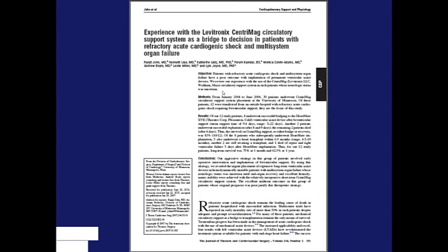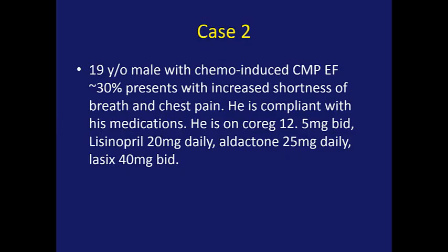So this article actually looked at 12 patients who were transferred from the outside. They implanted CentriMags in all 12. 4 of them died, but 8 of them successfully went on to HeartMate 2 devices. So that's pretty good for patients who are in straight shock.